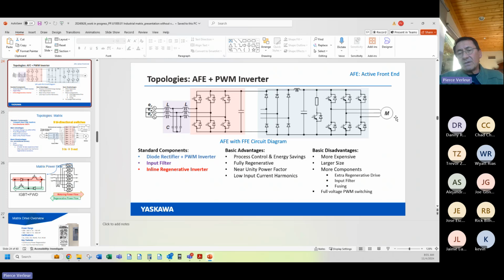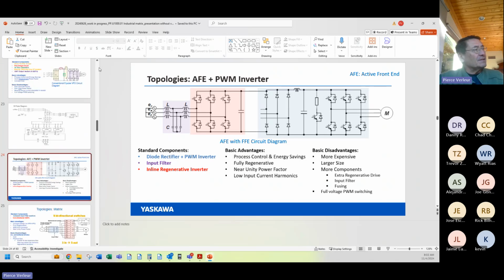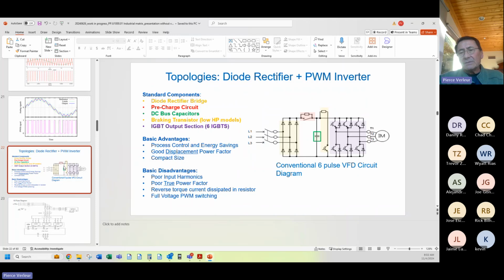I'm going to ask you to stay with me for another 7 minutes because I need to explain the last item on this presentation. The fact is that boosting the voltage on an active front end is necessary to maintain power factor performance. It's not designed in to boost voltage to the motor. Again, the bottom line is that we've been fine with the voltage drop of the variable frequency drive ever since the days of Toshiba in 1983.